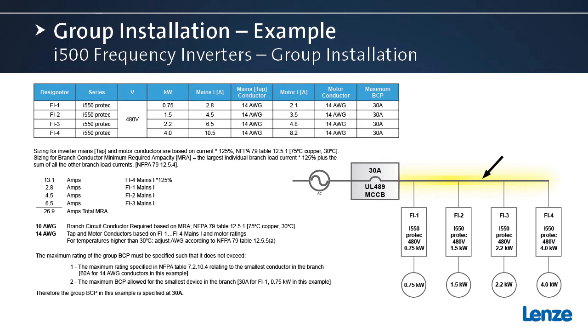To size those conductors, we have to do a calculation. The calculation is defined in NFPA 79 12.5.4. What we have to do is take the largest load in the branch, so in this case the 4 kilowatt inverter, mains current of 10.5 amps. We multiply that current by 125%, and then we add the remaining mains currents. And in this example, we get a total of 26.9 amps. That is the minimum required ampacity. We must use that value to size the conductor.